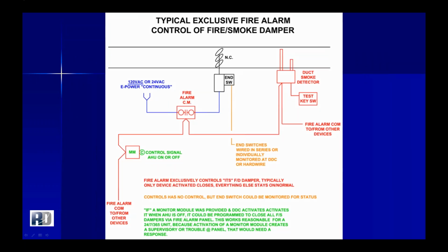So here, diagrammatically, we've got the duct smoke detector that detects smoke, and it sends a signal to the fire alarm panel, which sends a signal to close its associated damper. You also have this monitor module here that is basically listening. So Dave kind of went over how the control module sends out the signal. The monitor module is listening. So when the air handler, for example, goes down for any reason, let's say a low limit safety or static pressure, or it's just down for maintenance, this monitor module sees that this system is down, and it sends a signal back to the fire alarm panel saying, hey, this system's down. The fire alarm panel sends out a signal for all the dampers to close. So the fire alarm is closing the dampers for reasons related to the control side, not just the fire alarm side. This is typically something that's done more in a 24/7 building.